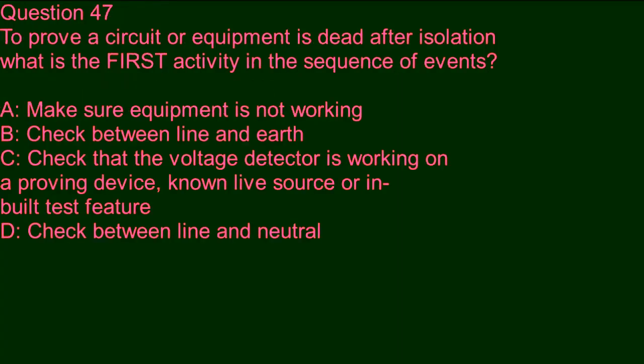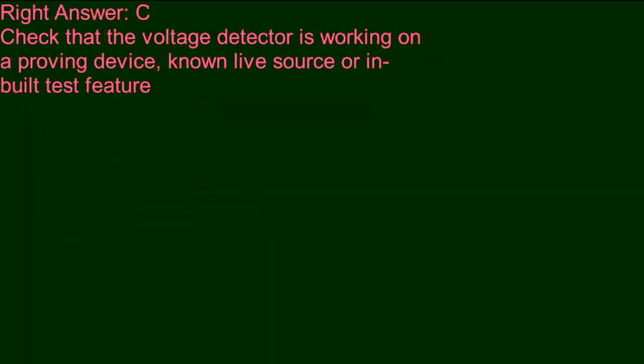Question 47. To prove a circuit or equipment is dead after isolation, what is the first activity in the sequence of events? A. Make sure equipment is not working. B. Check between line and earth. C. Check that the voltage detector is working on a proving device, known live source or in built test feature. D. Check between line and neutral. Right answer, C.